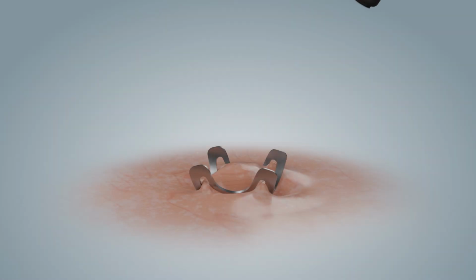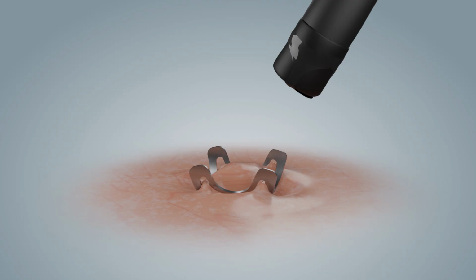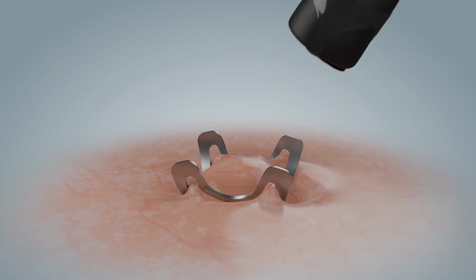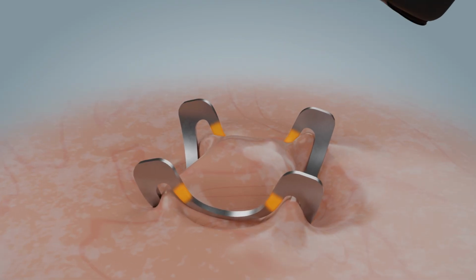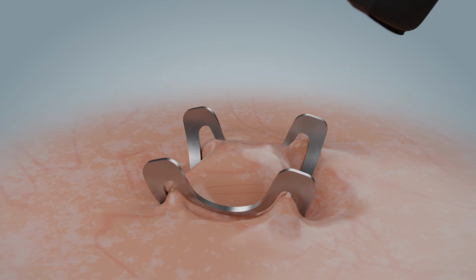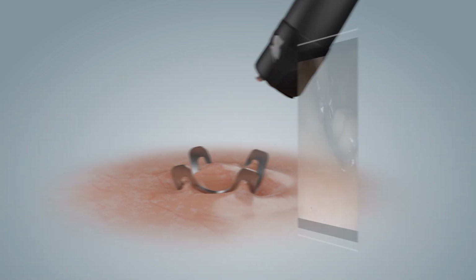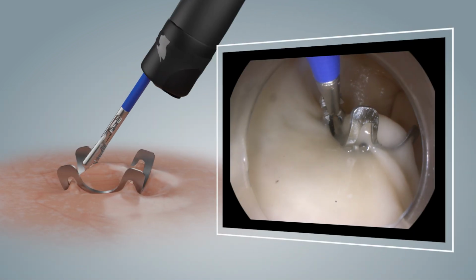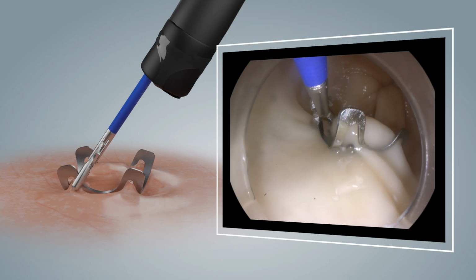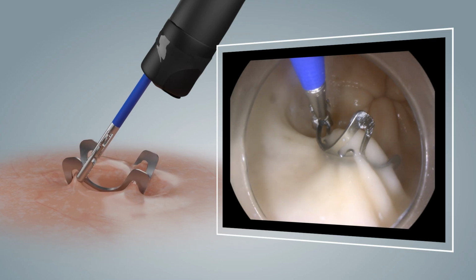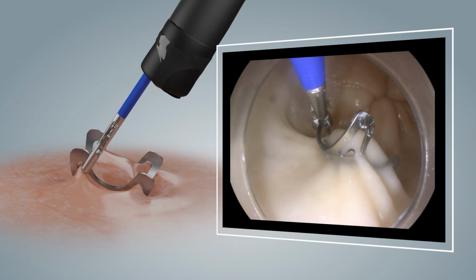Advance the endoscope with the mounted remOVE shield to the application site. Ensure the thin parts of the clip are easily accessible. Otherwise, the clip must be dissected free. A grasping instrument can be used to bring the clip into position before the procedure, so that the thin parts are exposed. If body fluids prevent good contact, rinse the clip before attempting to cut.